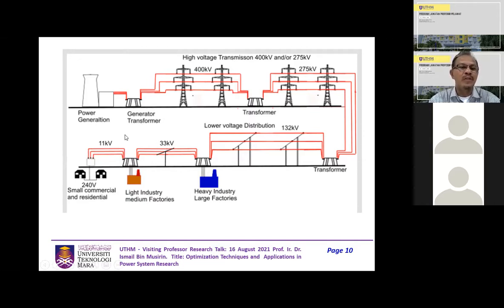We have the vertical power system. Power generation will be connected to a generator transformer, normally installed in front of or at the outlet of the power station. In Malaysia, the power station in Peninsular Malaysia will generate around 20 kV. This supply is connected to the transformer to make sure the supply level is at par or compatible with the transmission line capacity, so it will be stepped up to around 400 kV depending on the transmission line capacity.